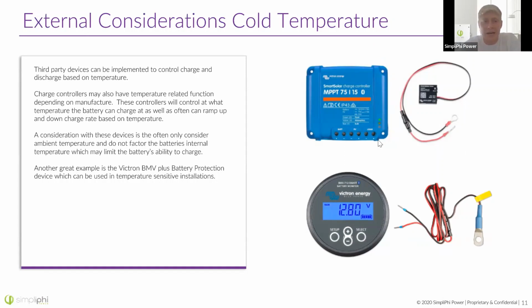Now, the only downside here is the temperature sensors used in these devices are external to the battery. So this is not sensing accurate cell temperature right on the cell level, it's just outside the battery case, which can differ sometimes significantly. On the bright side, that's going to differ in a more protective way. If it's cold outside, the batteries are always a little warmer than the ambient temperature, so this in turn is going to sense the colder temperature and be more on the protective end.